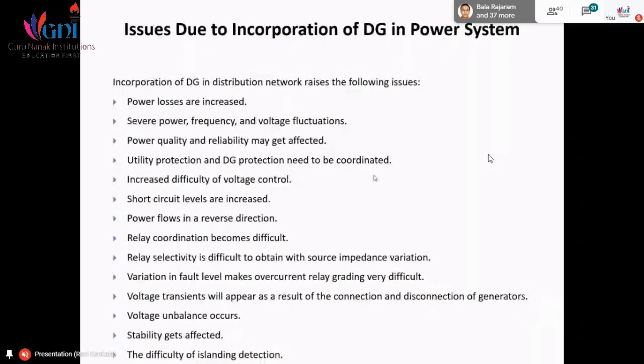Intentional islanding is done by the customer itself. The customer deliberately disconnects the DG from the utility or grid and utilizes the power generated by the DG for its own application, for its own load. That type of operation is called intentional islanding.